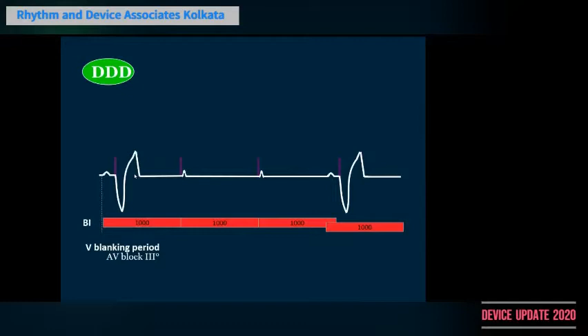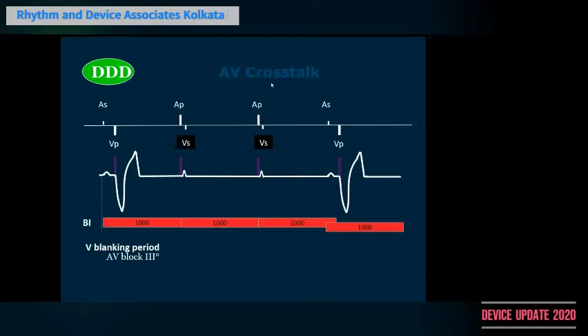Suppose you look at the second complex, an AP, an atrial pacing spike. This atrial pacing spike can actually sometimes be detected by the ventricular chamber. If that happens, it can lead to inhibition of ventricular pacing. You see here, there is an atrial pacing spike given and it has been simultaneously detected by the ventricular chamber and has been marked as ventricular sensed. And because the chamber sees it as an intrinsic event, it leads to inhibition of pacing. So if your atrial pacing spike is very powerful and your programming is not adequate, it can actually be sensed by the ventricle. This is called crosstalk, and this is a very dangerous phenomenon because, as you can see, in a dependent patient, it can lead to loss of pacing.